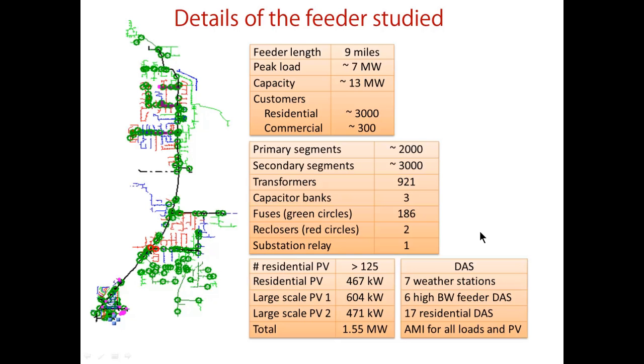coordination study. For the protection itself, it is these 3 parameters that are most relevant: the large number of lateral fuses, the 2 reclosers, and the substation relay. And we will be studying the coordination among each of these devices for different types of faults for different PV scenarios.